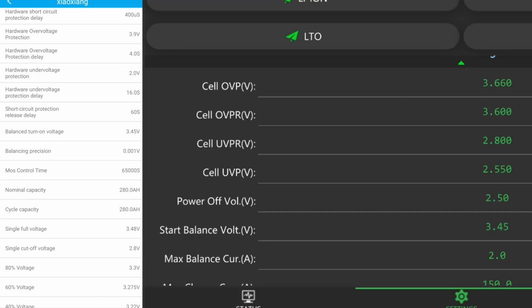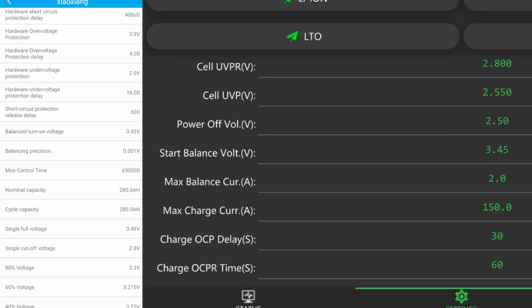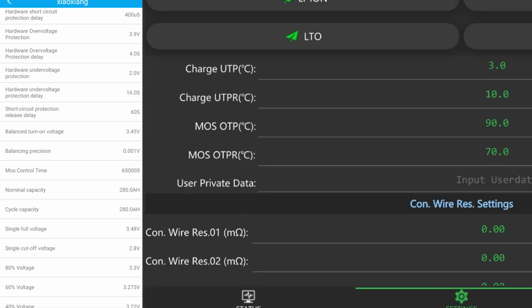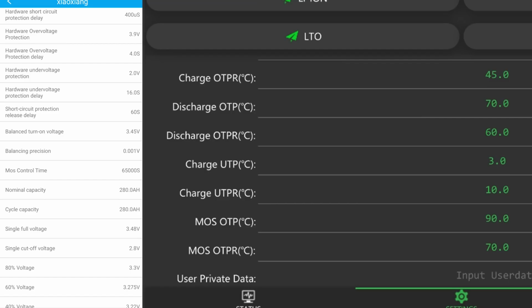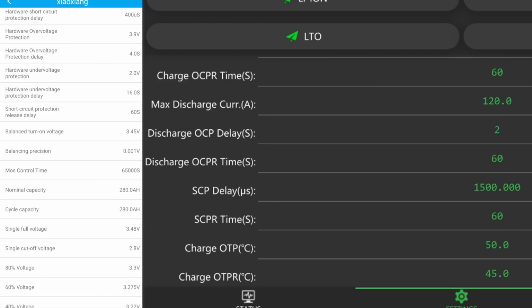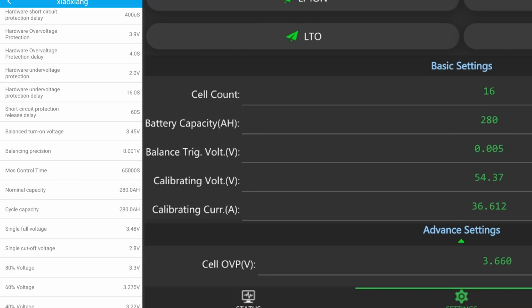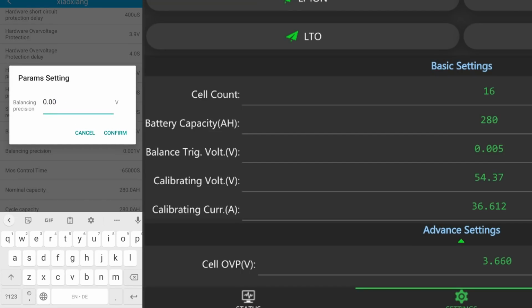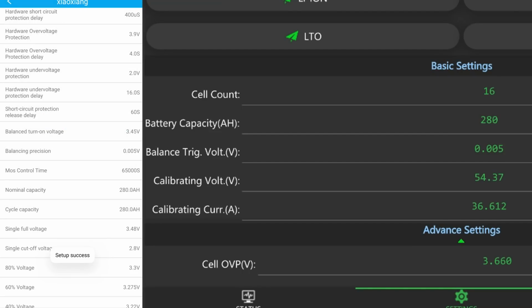The start balance voltage in the JK-BMS is 3.45, and I'm sure it's the same here, 3.455. Let's change this one to 1 millivolt deviation on the QUCC. And can we not set... I can't remember. I can't see it here, it's all the way up in the basic settings: balance trigger voltage, 5 millivolt. 5 millivolt is totally fine. I can potentially set this one as well in the QUCC BMS.